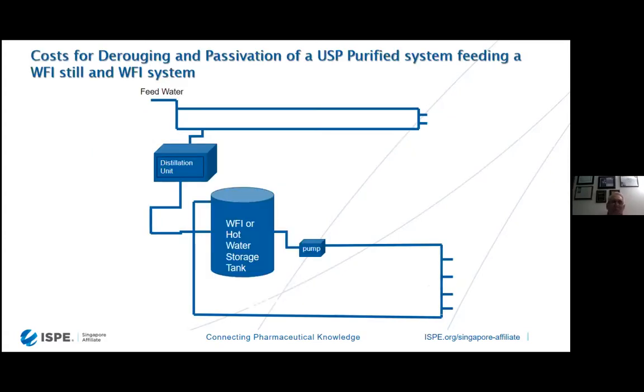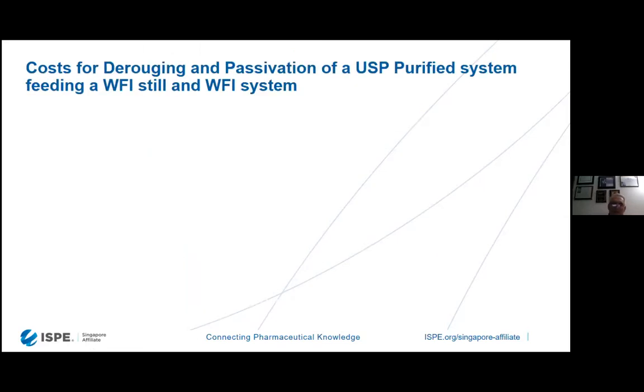So this is a typical water system we're looking at for WFI. We have a feed water system running purified water off of that purified water line, running into a distillation unit like a multi-effect still or a single effect still, and then running into a hot water storage tank, out to our pump, out to our points of use and back. So that's typical for a WFI water system. It may not be exactly like yours, but it is typical. Some systems don't use multi-effect distillation. They'll use vapor compression stills, and they can use softened water, and they don't need purified water. Usually they'll go purified water to distillation, multi-effect still, and then to WFI.